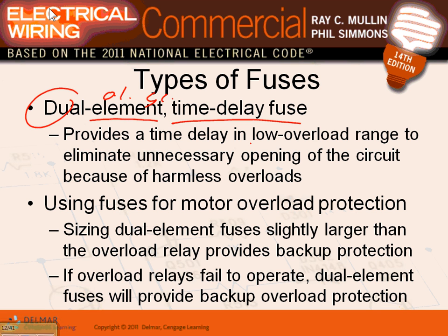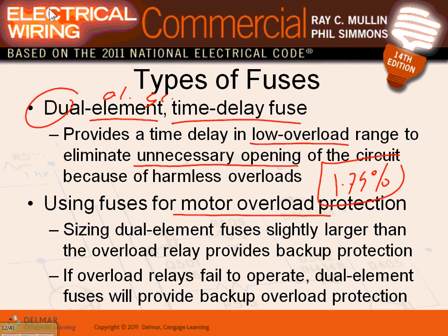So it provides time delay on a low overload range to eliminate unnecessary opening of the circuit because of harmless overload. This is a good application where you can put it on a motor. You put a dual element time delay fuse on the motor, and it allows you to start your motor without tripping on the inrush. So you can use it with motor overload protection. Slightly larger: if you remember the code size for motors, it's 175% times the full load current. What's nice about this is it gives you overload backup for your system. If the overload fails, then the dual element will take care of it.